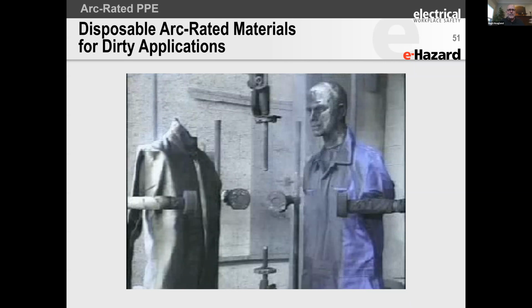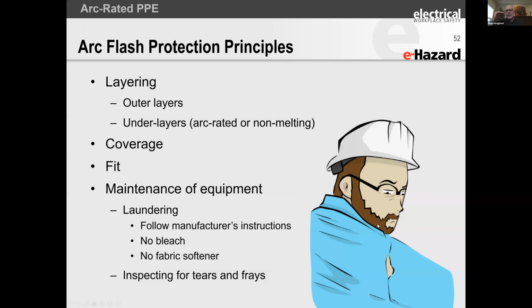You take those off because hydrocarbon loading can add to your burning, as we saw with that hydraulic oil. So for layering, the outer layers need to be flame resistant and arc rated, and the under layers need to be arc rated or non-melting. Cover as much of the body as you can, fit it comfortably, and follow the manufacturer's instructions on washing - no chlorine bleach, no fabric softener is the typical recommendation. One time with fabric softener doesn't remove flame resistance, and some materials aren't really affected by it. Just check with your manufacturer and see what they recommend.